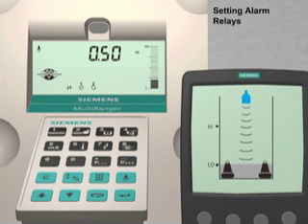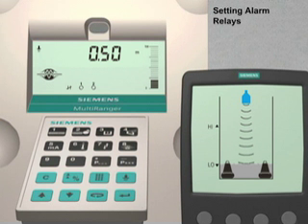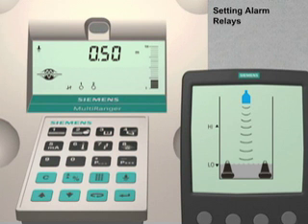The PDA graphic shows that the Multiranger is actively measuring the liquid level in the vessel. We can also see on the Multiranger display the icons for the first two relays. The hollow circle indicates that these relays are active but not currently engaged, meaning the pumps are not running. Since the first two relays are being used to control the pumps, we will use relays 3 and 4 to control our alarms.